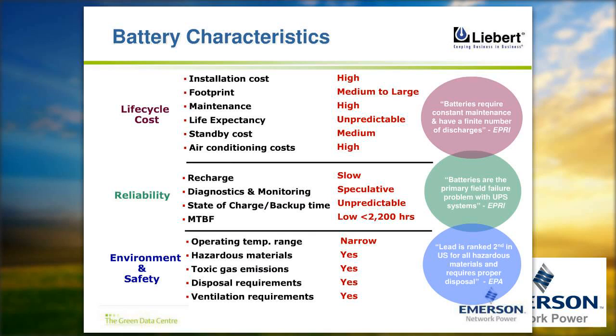Now, the battery is also a very important factor to be considered because it's consumable. In India, the batteries available are rated for about 250 to 300 cycles of discharge, and they need to be replaced or replenished every three years or so. That also impacts a lot of environmental and safety factors. We recommend that we should use longer design life batteries, so the replenishment does not happen so often. And we also recommend using a hydrogen meter inside the battery room along with the fire suppression system, because many a time a data center gets impacted because of a fire issue with the battery.